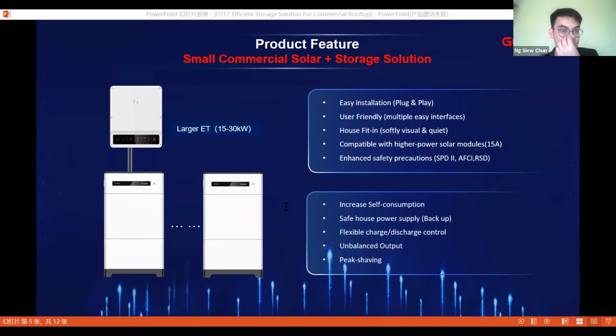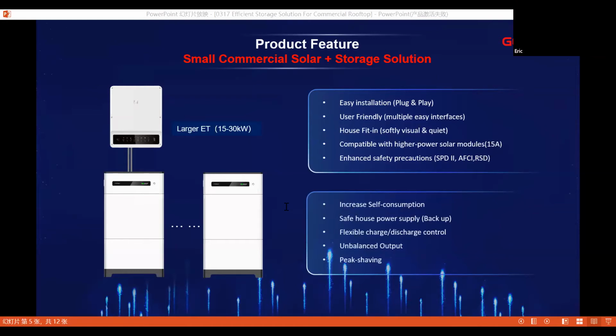What is the maintenance for this storage system, does it need frequent checking? Mostly, if your storage inverter system charges and discharges every day, you don't need other maintenance, since it works continuously, charging during daytime and discharging at nighttime. With one or two cycles each day, no special maintenance is needed, just check the monitoring data, and if the battery isn't charging or discharging normally, check it. If your system doesn't work every day, you may need to charge or discharge the battery every 3 months as maintenance.